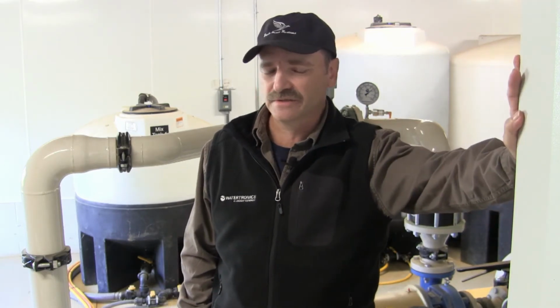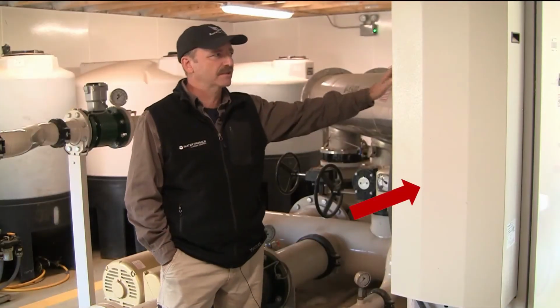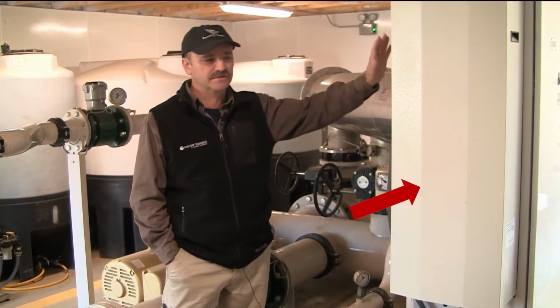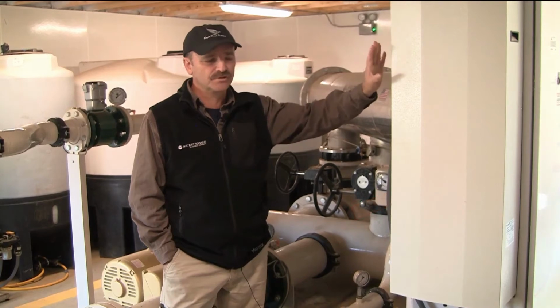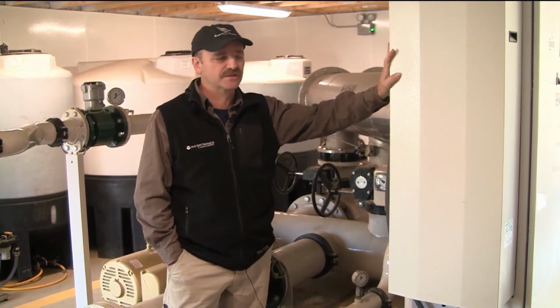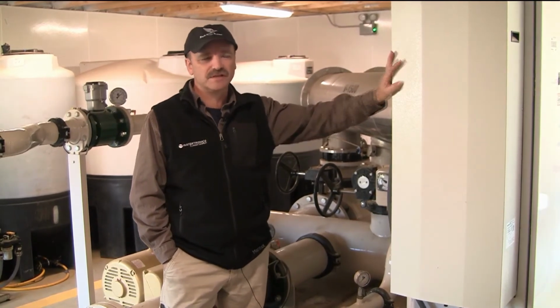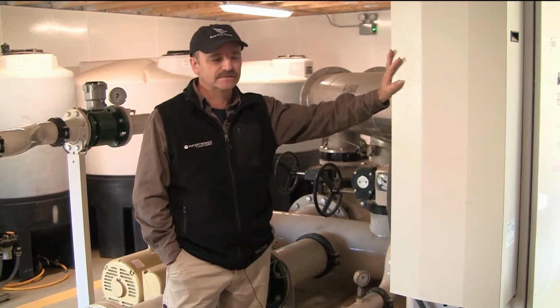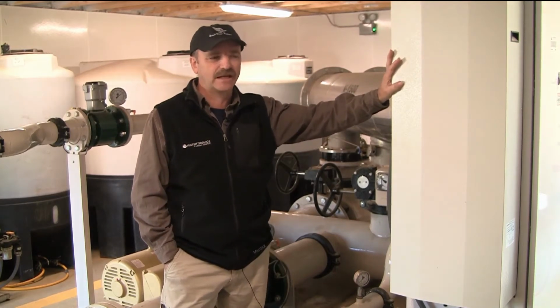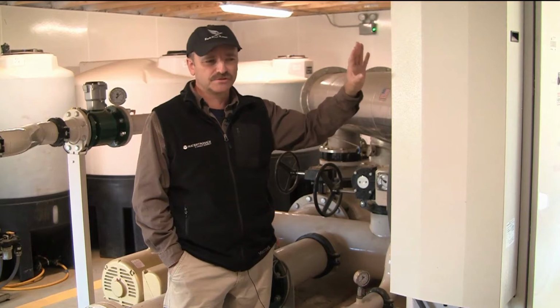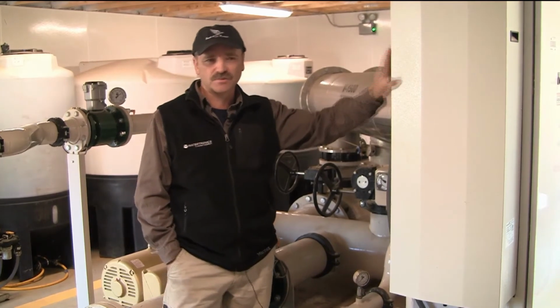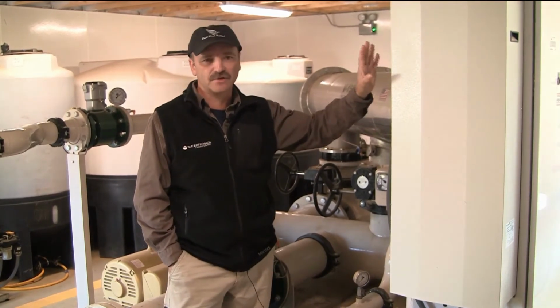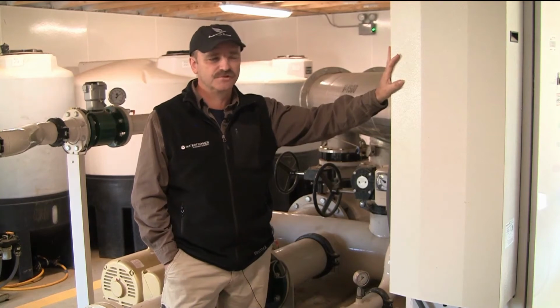So on this unit here, we have the heat exchanger, which is basically a radiator, which is cooling the air inside the cabinet that's created by the variable frequency drive and all the other electronic equipment that's in there. So one of the important things to remember as the colder season comes in is this will freeze and break, and the water can end up inside the cabinet. So remember to turn your heat on or get a heater into your pump station, because these are highly vulnerable to freeze and damage.